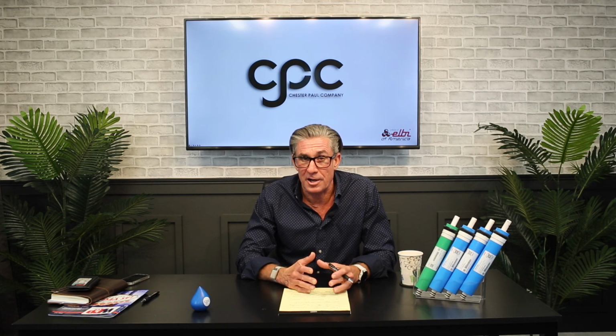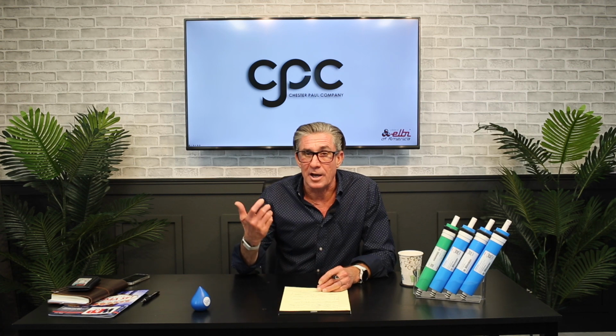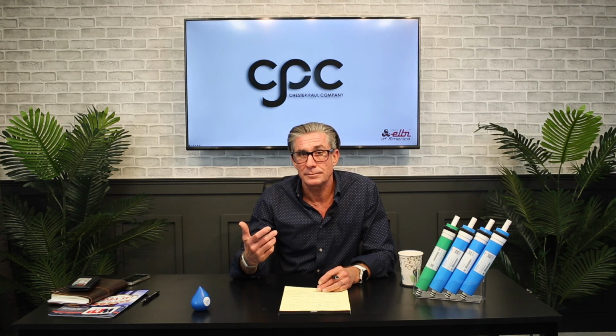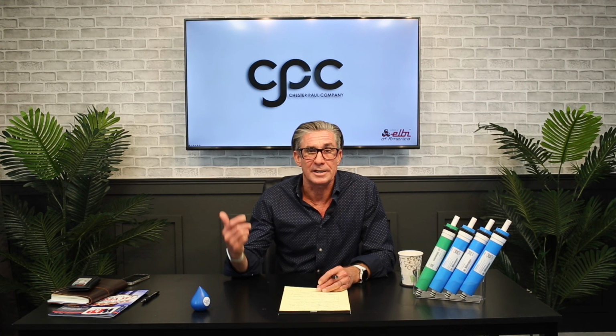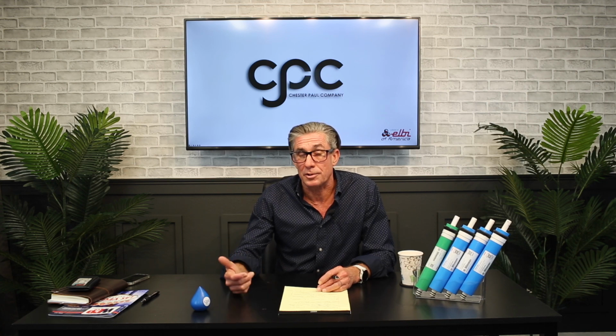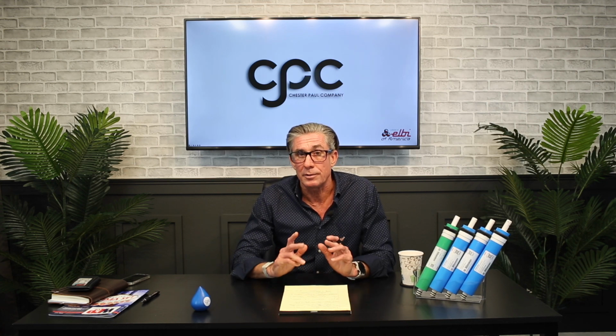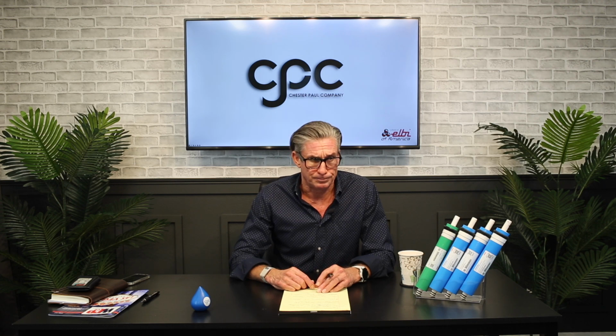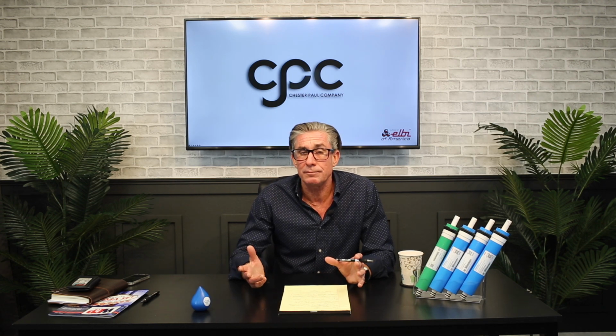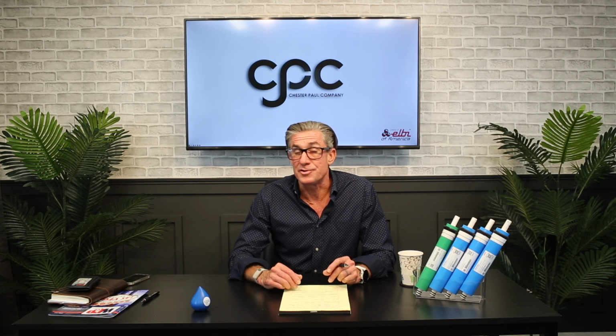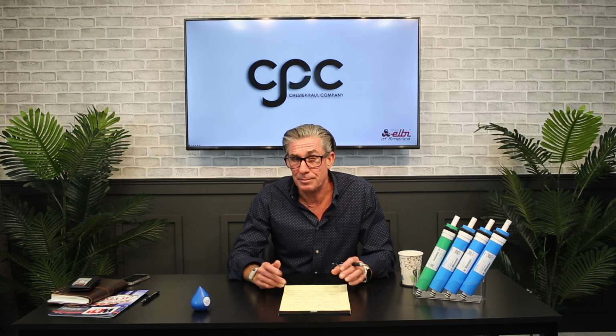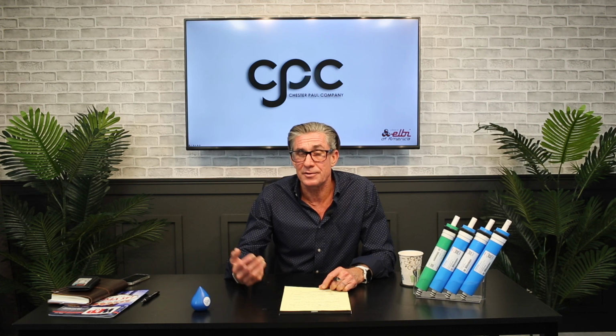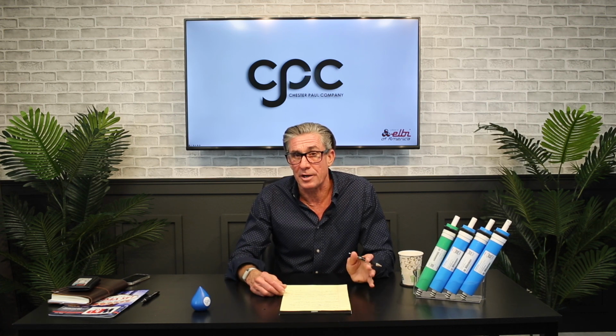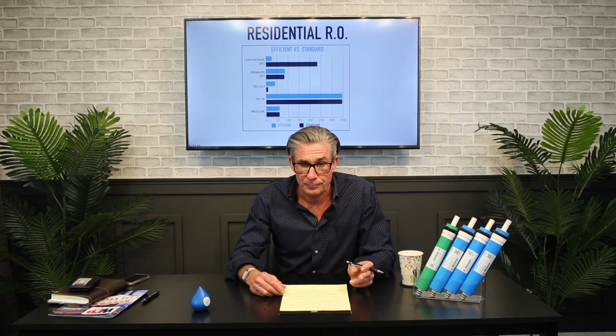Recovery defined is basically you've got a gallon an hour of product to a gallon an hour of waste or concentrate. That is a 1-to-1 recovery. When you hear 5-to-1, 4-to-1, very common in residential RO, that is open spigot, again, no back pressure, 4 gallons or 5 gallons concentrate to 1 gallon product or drinking water.